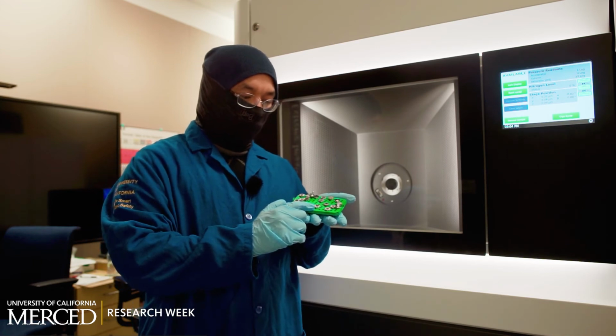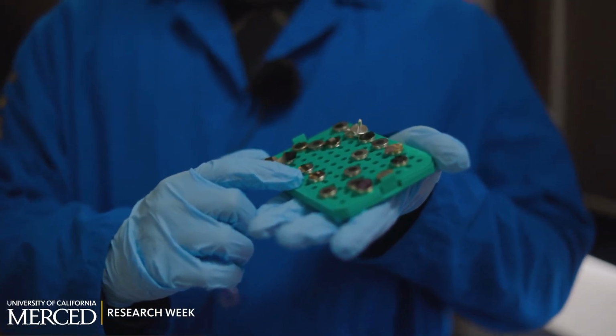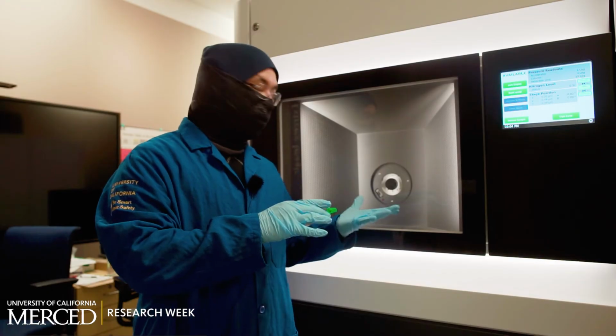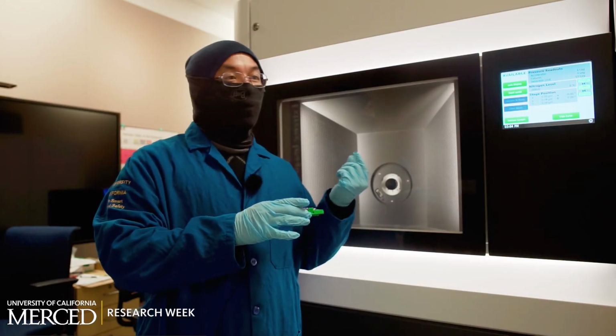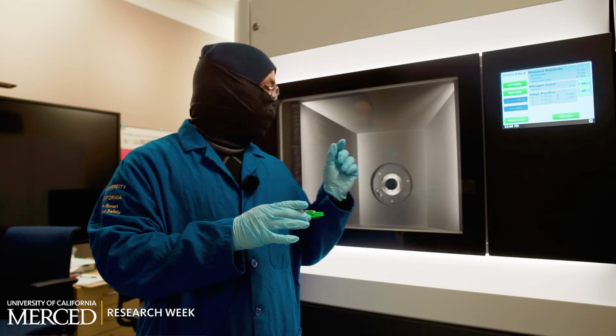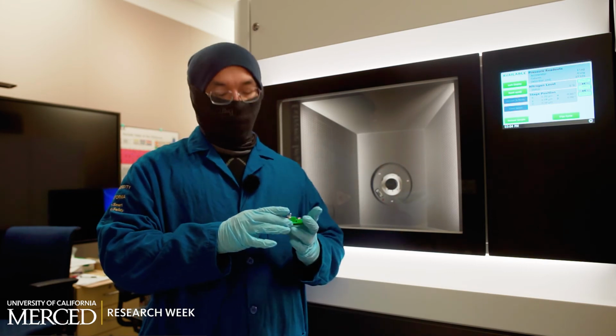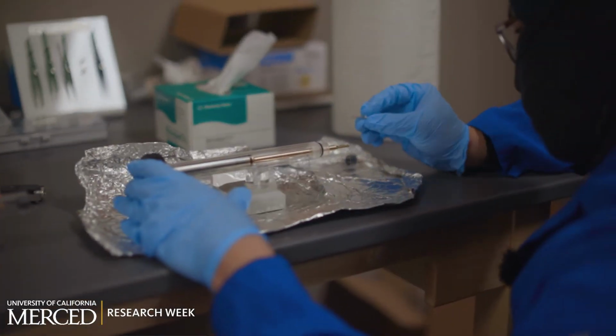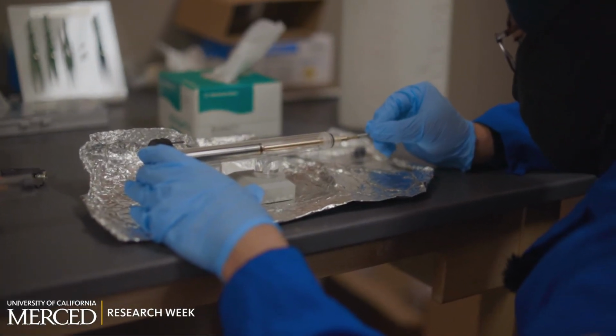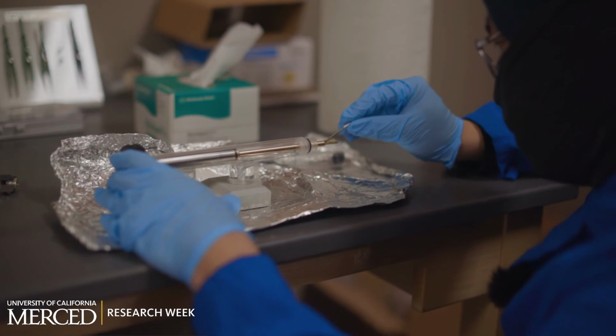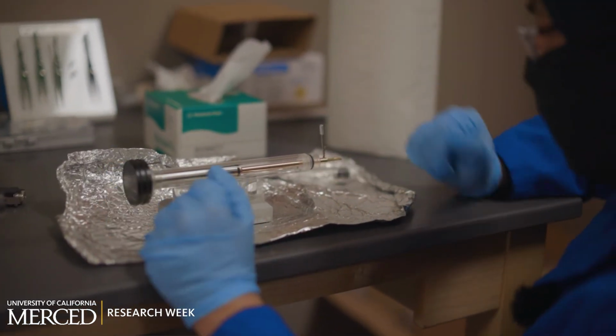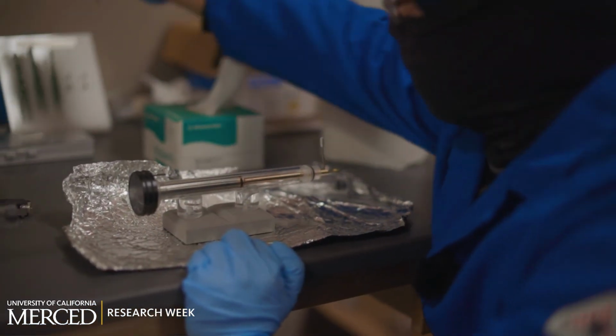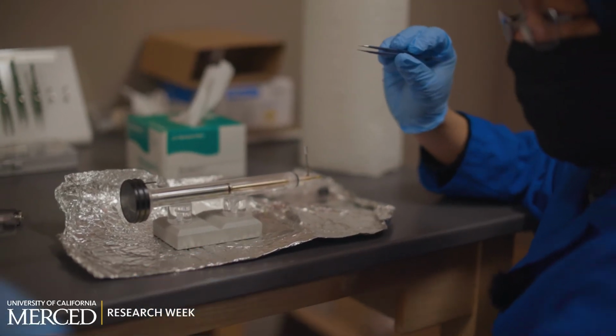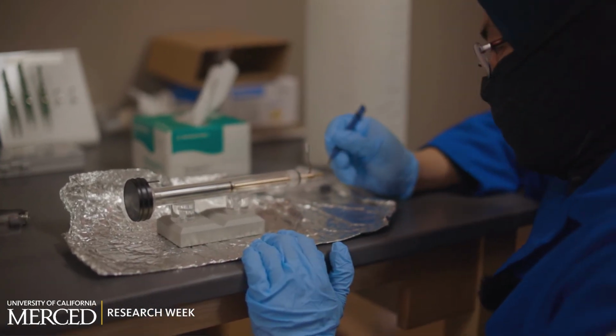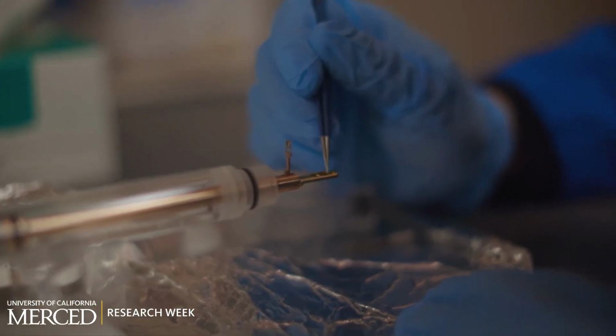So you see these grids here. This is about the approximate size you'll have for the holder. So I'm going to take out this holder so you can see how thin and how small we have to put on the grids, so then we can put it into the microscope. To put the grid on this sample, we use this tool here. Insert, lift up sample here. And then we would grab one of these tweezers here. Then I'd grab one of the TEM grids, and you could see I'll place it onto here, center it. So I'm going to align the small pin to this arrow key here.